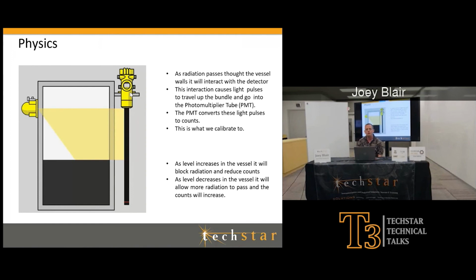So to get a little more into it, basically as radiation passes through the vessel walls, we're going to talk about scintillator technology first. It's going to be interpreted into light pulses as it passes through the wall, and the gauge is seeing those light pulses, and those light pulses are going to be turned into counts. Okay, so that's the unit of measurement the gauge is seeing. You're going to hear when you hook up to a gauge and you're doing your calibrations, you'll see counts on your screen. That's the unit of measurement.